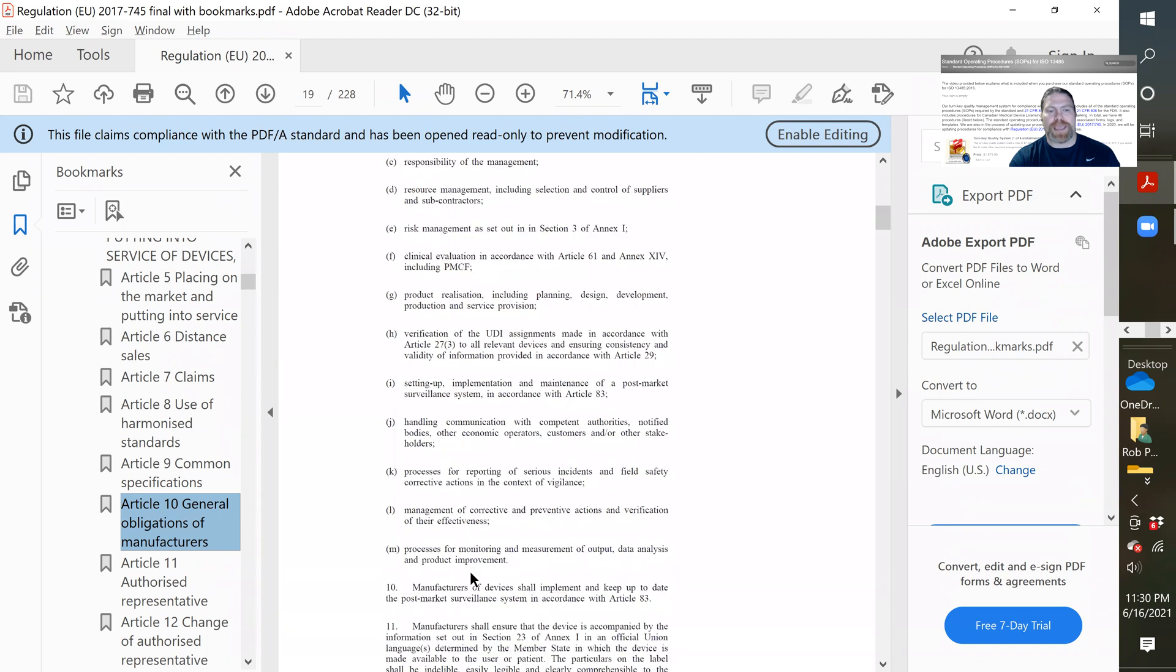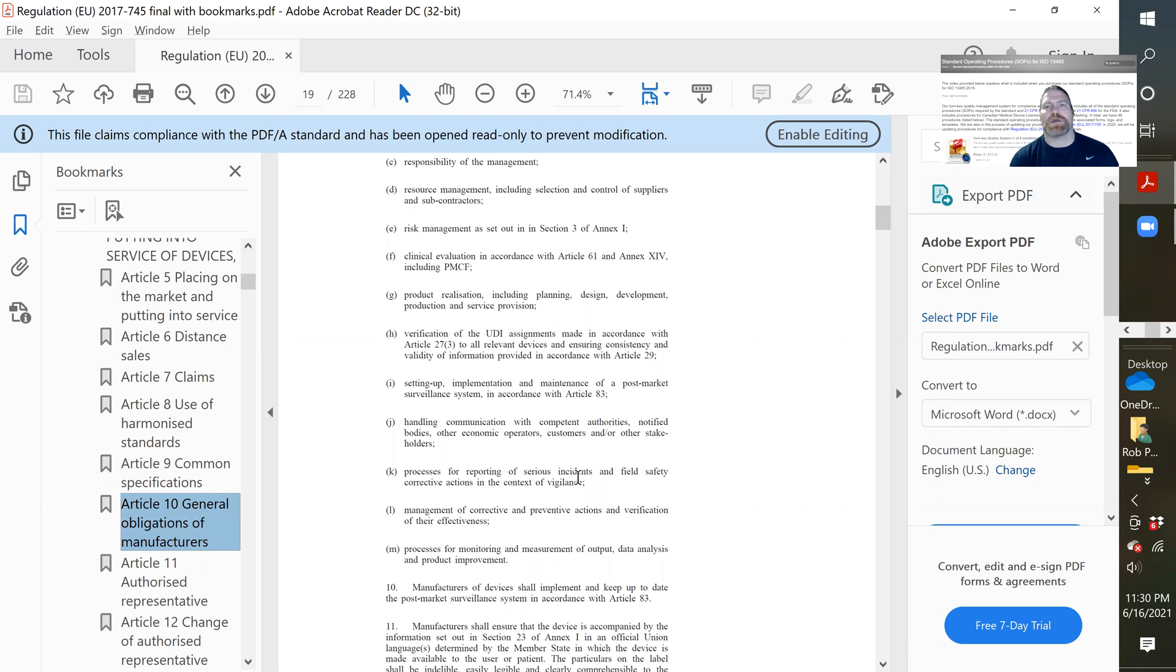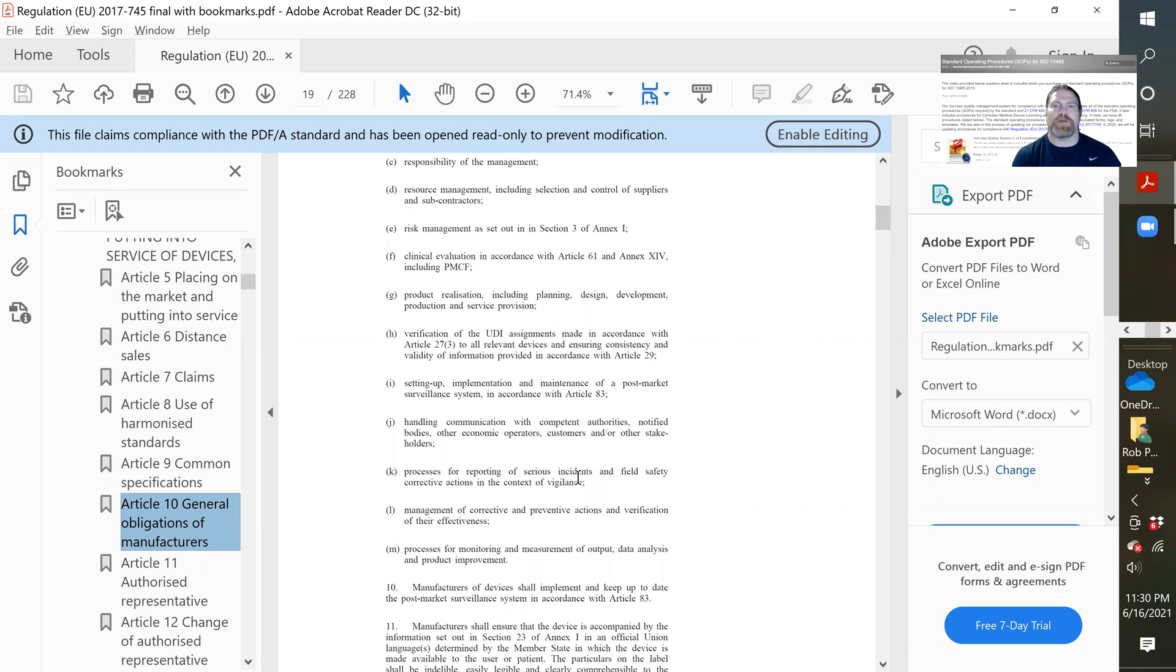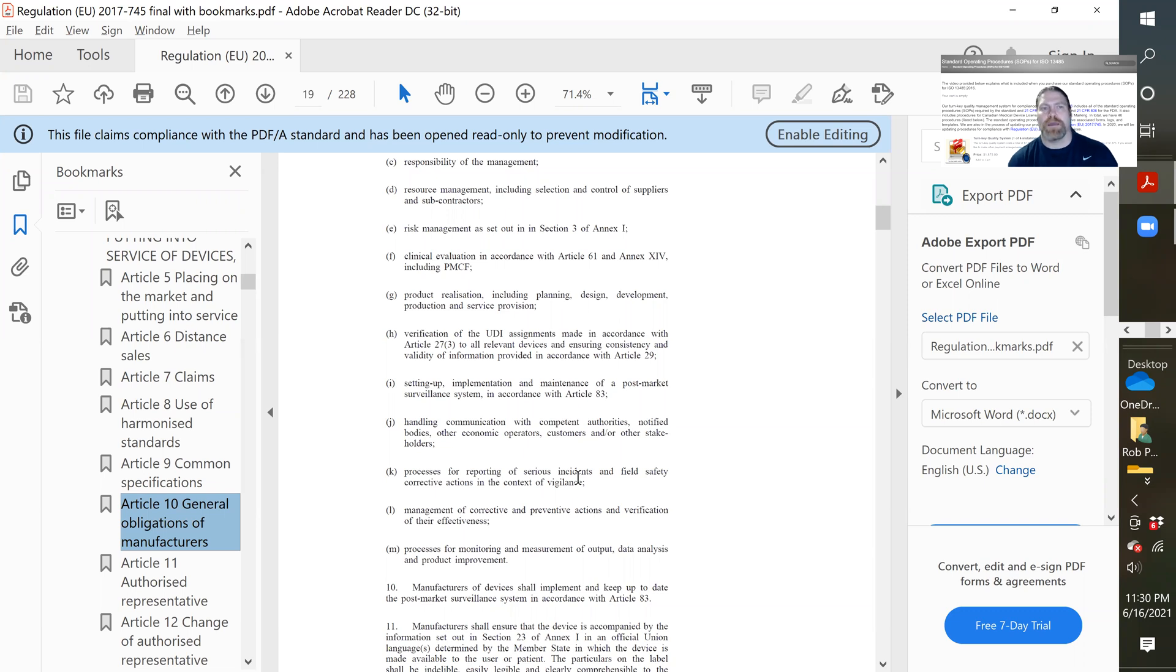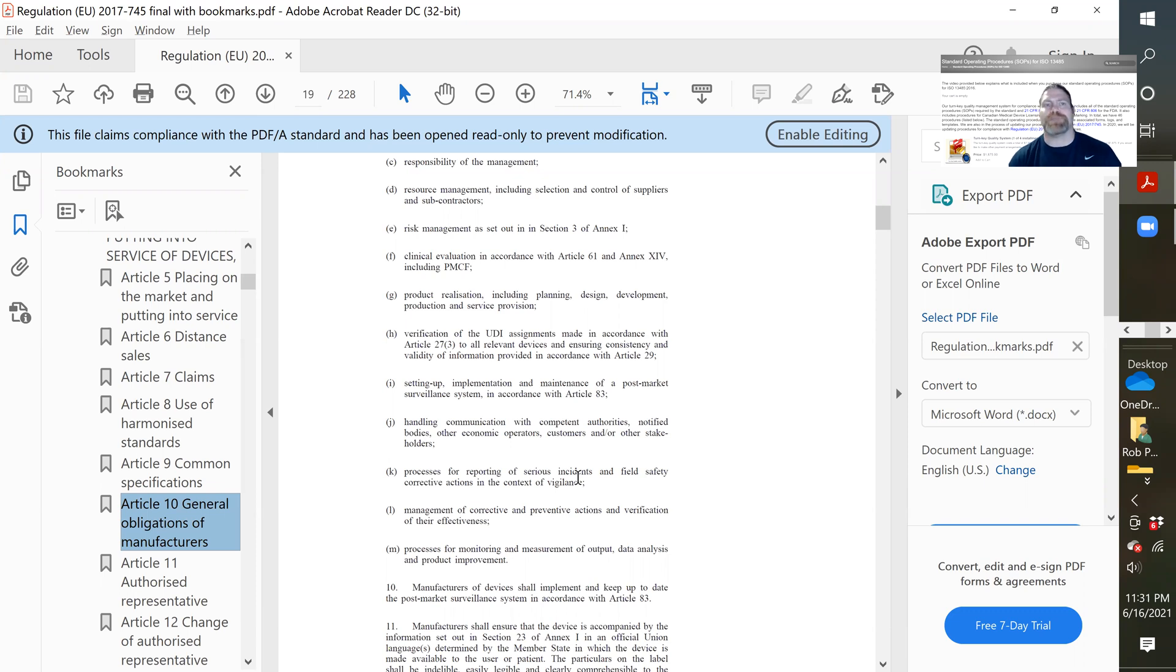I think there are only like eight places in the entire MDR where it talks about calibration. And they're talking about the classification of class one devices that have a measurement function. And what the notified body would look at is part of the process for giving you CE marking. But there isn't a specific requirement for calibration in this section. So there's no update that I had to do to the procedure to make it compliant with the European regulations.